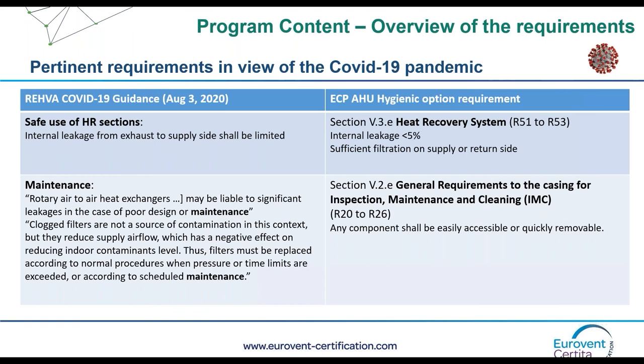Also, in this guidance document from REHVA, there is a note on the maintenance. Maintenance is really important because, for example, if you do not do maintenance often, the pressure drop of your filter will increase, and then this will have a negative effect on the supply airflow. It will reduce the airflow, and as we have seen, one of the main requirements is that sufficient airflow, sufficient fresh air should be provided in the building in order to mitigate the risk of virus propagation. So maintenance is key, and as we have seen, this standard provides a set of very precise and complete requirements on inspection, maintenance, and cleaning for all components, and namely, any component shall be either easily accessible or quickly removable so that it can be maintained and cleaned.